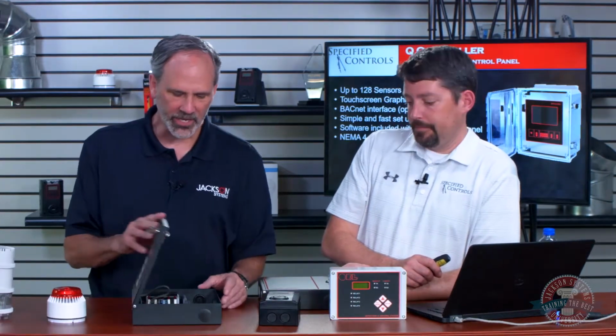One more thing. Is there a transformer in the panel? No, there is not. It has to be externally connected. We always include the transformer size for the number of sensors when you ask us to help put together a system. On our control drawing, it has the math that shows how we got to the transformer size. It shows 6 of this sensor at 0.8 amps and 8 of these sensors at 0.8 amps and the panel at 0.4 amps or whatever it is. And so it shows you exactly what size the transformer needs to be.